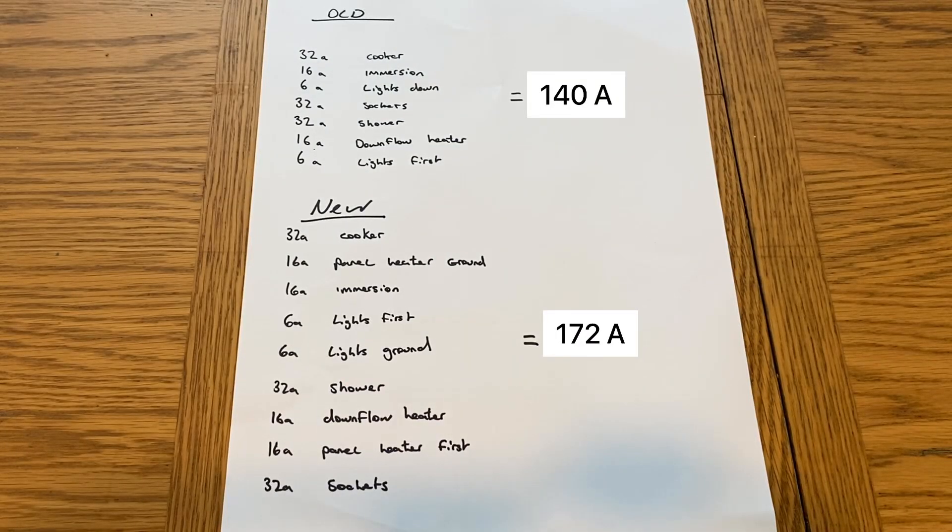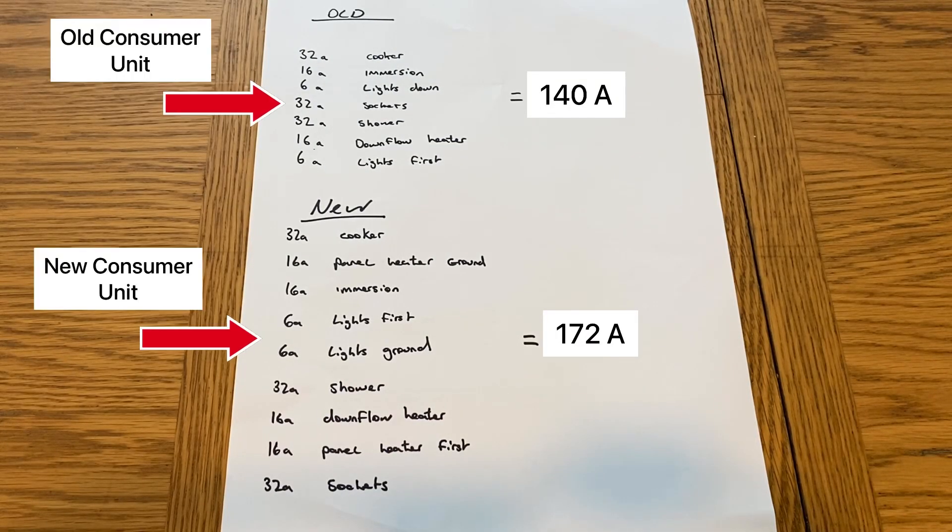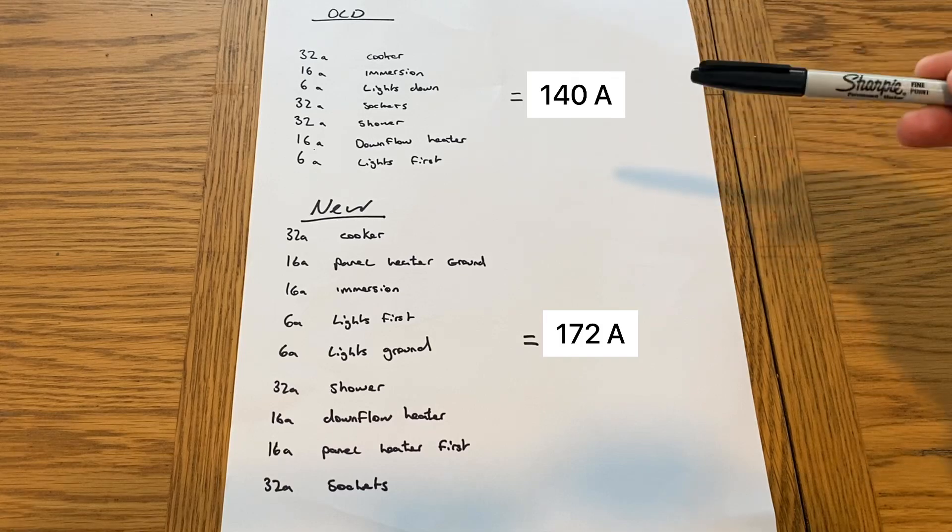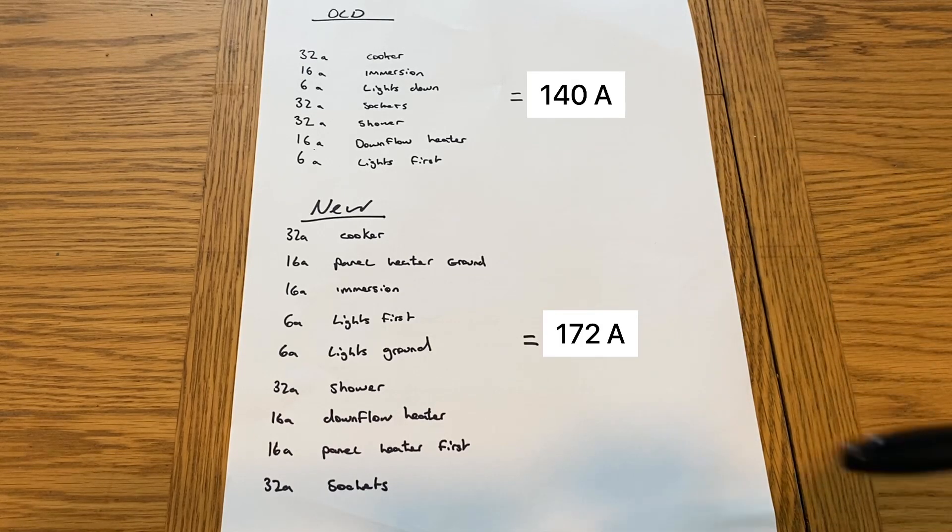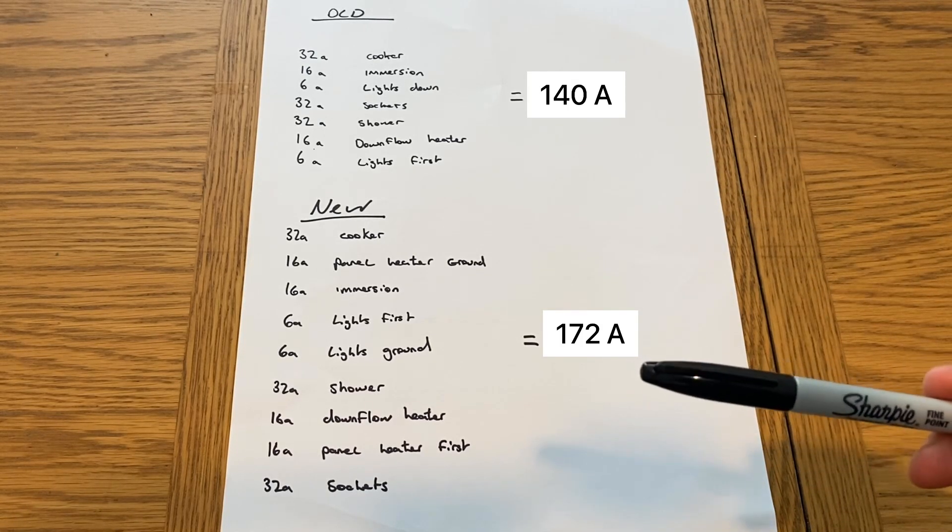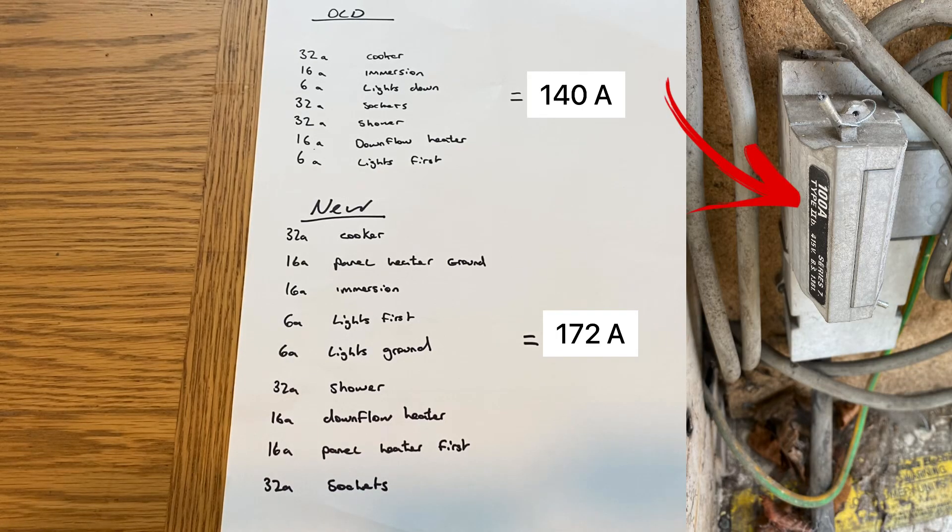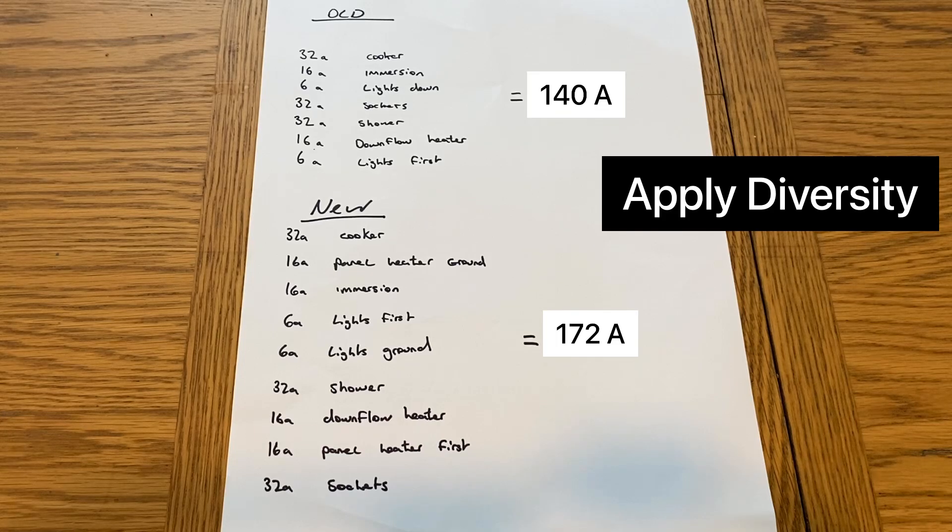Just before we move on to actually doing our calculation, just wanted to show you what these would equal if we didn't apply diversity. Our maximum demand for the old set would be 140 amps and for the new setup would be 172 amps. Now that's not going to be any good to us because we have 100 amp cutout fuse. However, what we're going to do is we're going to apply diversity because not everything will be on 24 hours of the day every day of the year using its full load current.